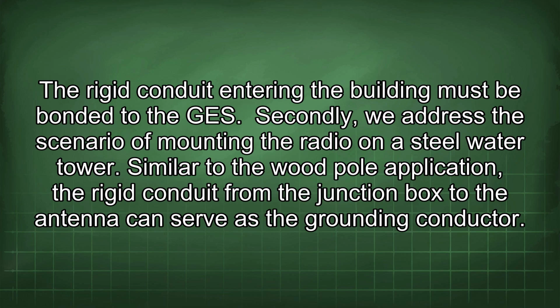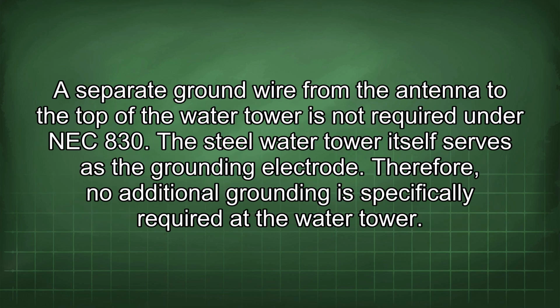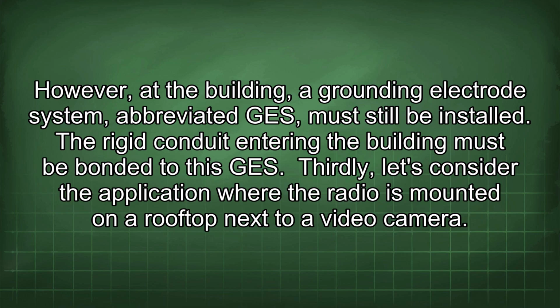Secondly, we address the scenario of mounting the radio on a steel water tower. Similar to the wood pole application, the rigid conduit from the junction box to the antenna can serve as the grounding conductor. A separate ground wire from the antenna to the top of the water tower is not required under NEC 830. The steel water tower itself serves as the grounding electrode. Therefore, no additional grounding is specifically required at the water tower. However, at the building, a grounding electrode system, abbreviated GES, must still be installed. The rigid conduit entering the building must be bonded to this GES.